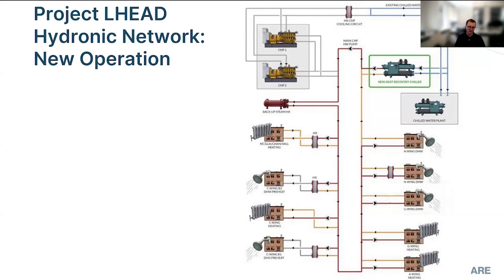And fortunately for this project, they also had an existing hot water network that was fed by steam from the gas-fired boilers and by some combined heat and power units at the hospital. And so the challenge here, or the opportunity here, was to add to their cooling capacity in the summer, and then to produce hot water they were already using to heat domestic hot water, terminal reheats, and other loads. And then in the winter to leverage the chilled water network to find additional cooling opportunities and heat recovery opportunities, exhaust being one of those, to provide base load for the heat recovery chiller to be utilized at full capacity year round, generating hot water at the efficiencies you described on the previous slide.